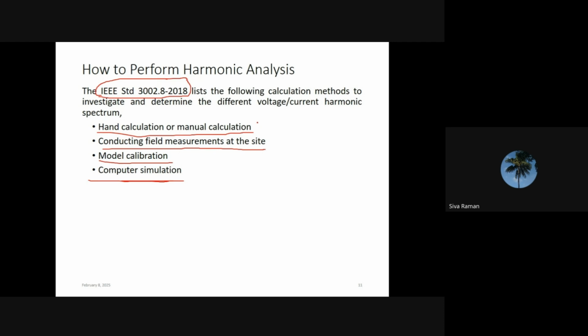Manual calculation method: before the introduction of computer simulation, mostly our previous generation power system engineers did the harmonic analysis through manual calculation. It is very useful for a simple system. For a complex system, it is extremely difficult to perform the harmonic analysis. And conducting the field measurement at the site is one of the practical ways to measure the harmonics, how much amount of harmonics gets injected.